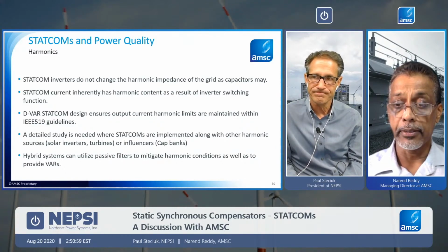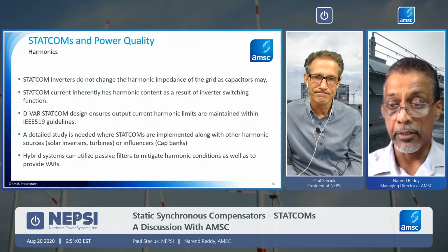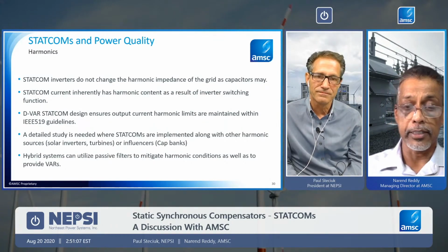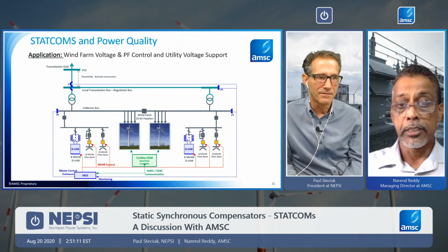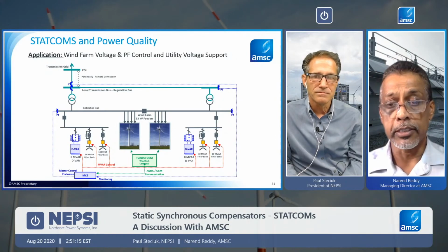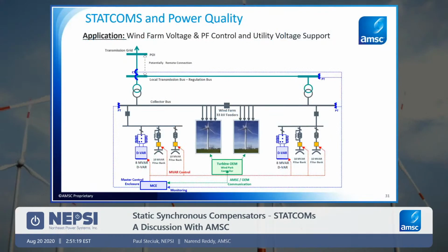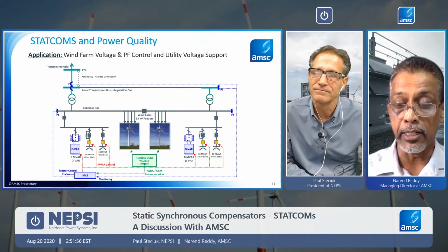And of course, if you have cap banks as part of the installation, they can always be detuned. And I know you guys provide those cap bank or harmonic filters as well. Just as an example, I wanted to show you this. This is a wind farm installation that is unique in that it is in a very harmonic-rich environment and in a very weak part of the grid. In this installation, the AMSC D-VAR as well as 4 capacitor banks had to be installed, not only to provide reactive power, but also because those filter banks ended up being significant harmonic filters, and obviously they are switched in and out under certain conditions.